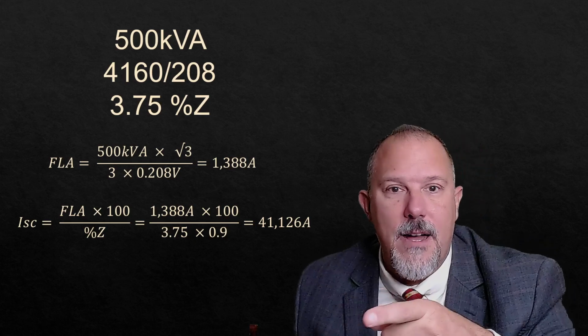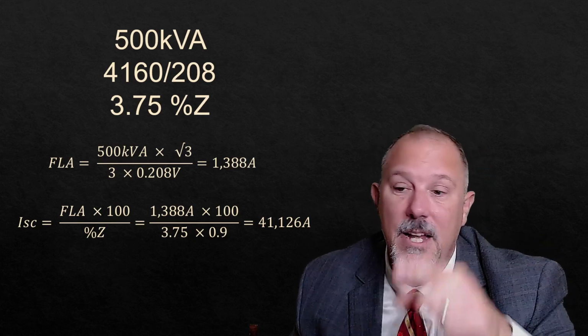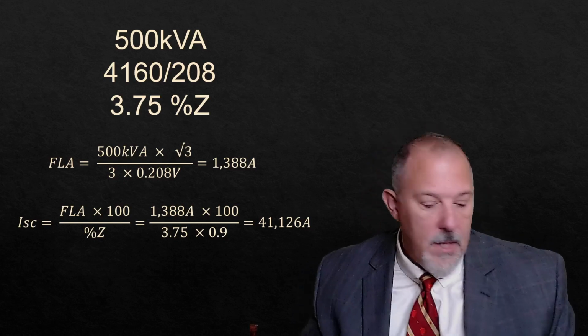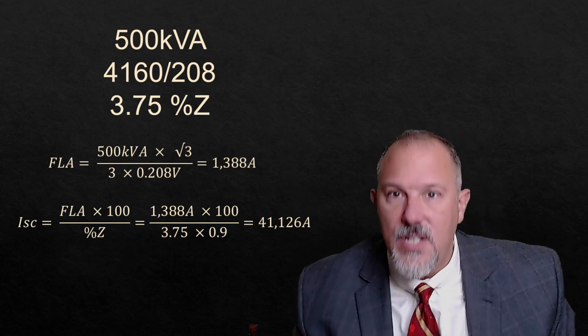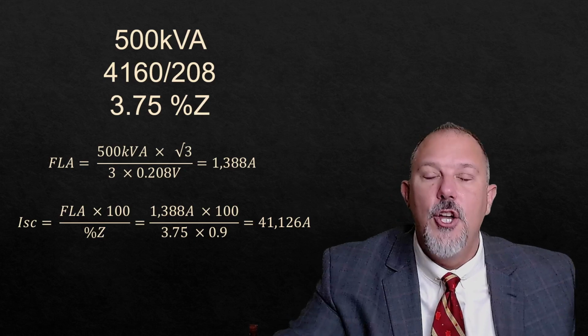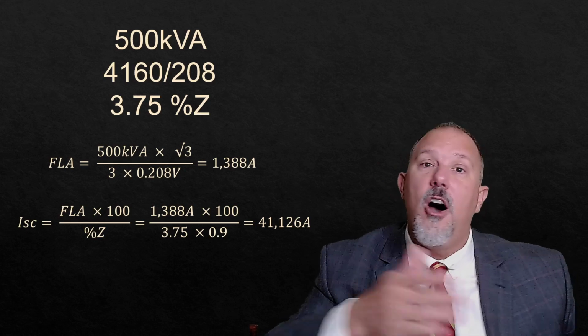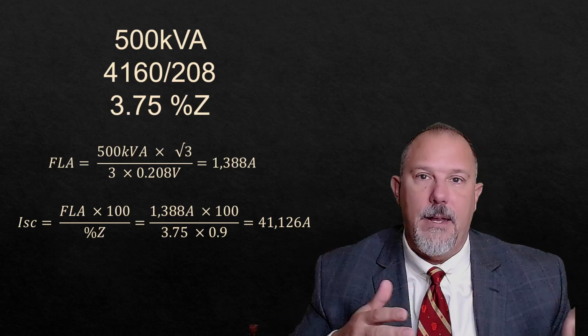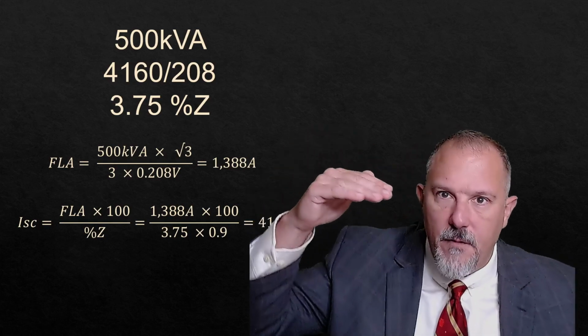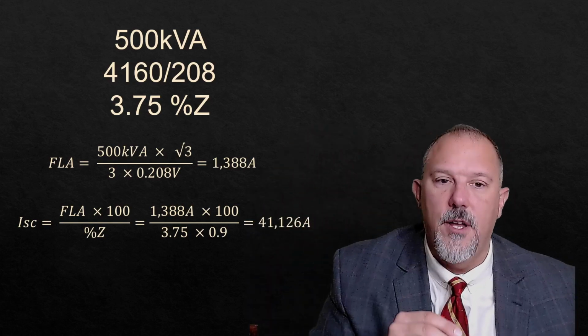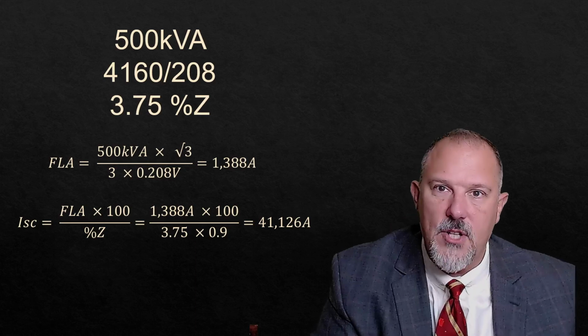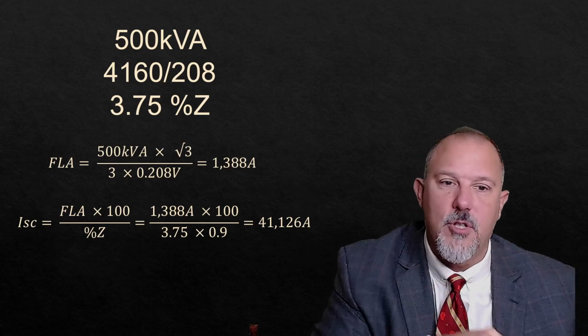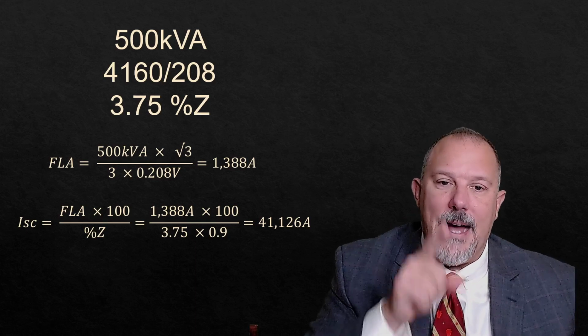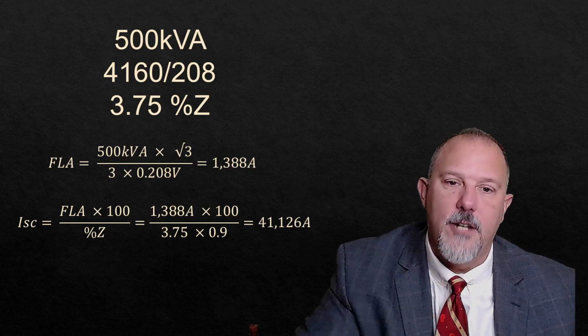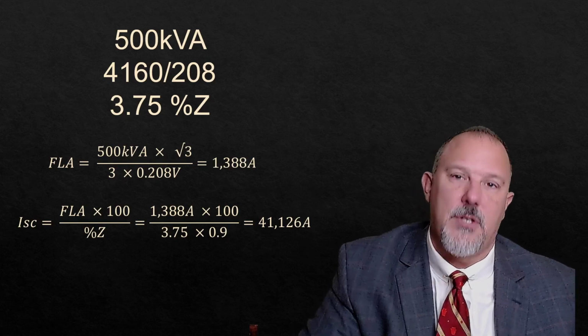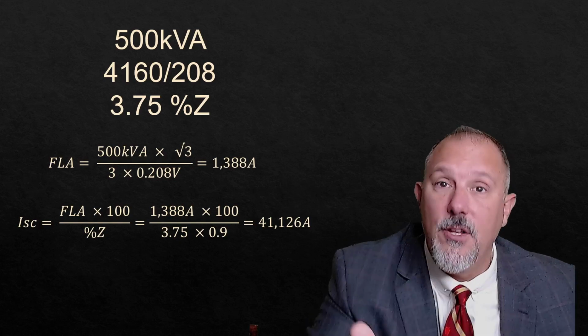And where did the 0.9 come from? 0.9 is, remember, when you see a transformer's impedance, it can be off by 10% on either end. So to get the maximum available fault current, I reduce the impedance by 10%, which is 0.9 times 3.75. And I get 41,126 amps. Now that's a manual calculation.